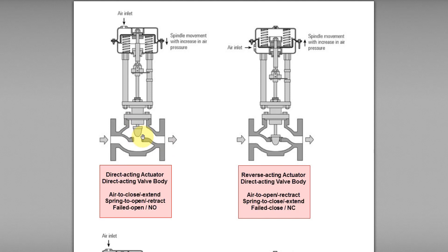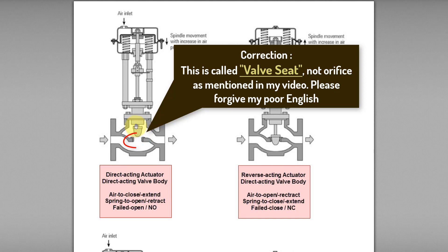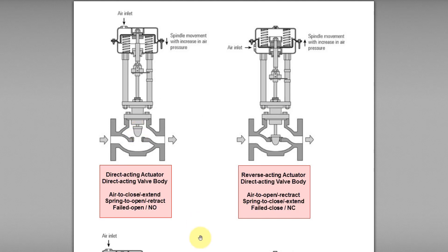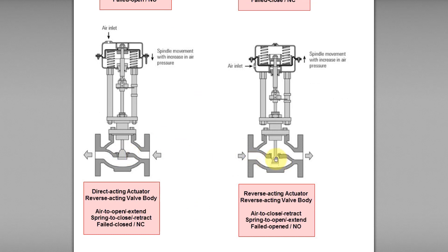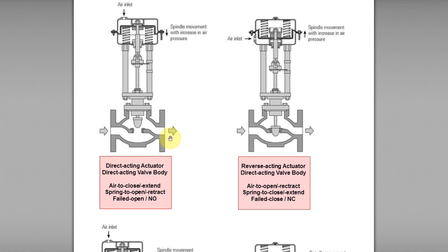For the valve body, how do we know if it is direct acting or reverse acting? We look at the plug location. If the plug is located above the valve body orifice, it is called a direct acting valve body. If the plug is located below the orifice, it is called a reverse acting valve body. In this example, these two plugs are located above the orifice — when the stem goes down, the plug closes the orifice — so these two valve bodies are direct acting. The other two control valves have the plug located below the orifice, making them reverse acting valve bodies.